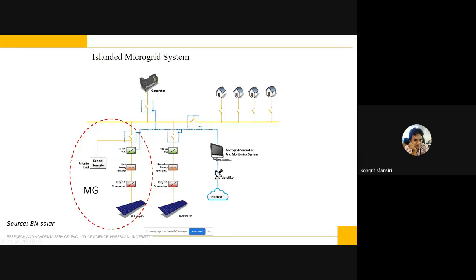That is the school and temples. How does the system work? Normally, the systems work together, because this PCS can work in both modes, grid-connected mode or islanded mode, and can be a current source or a voltage source. When the main system has a problem or the battery is nearly empty, with SOC nearly 30%, this breaker at the point of common coupling is open. When this breaker is open, this system can supply the priority loads. But when the battery still has high SOC, they can work together.